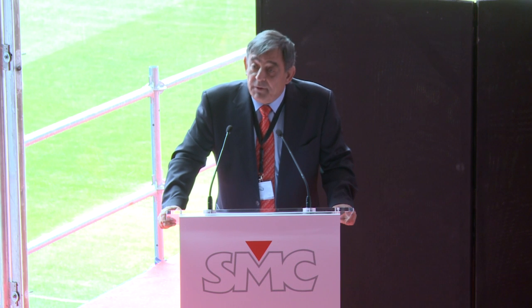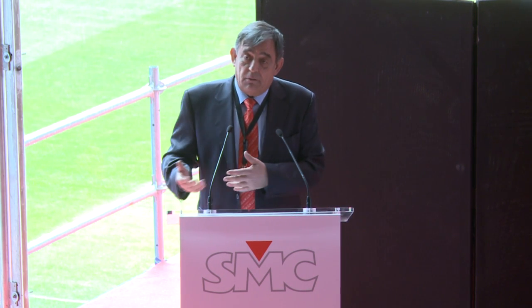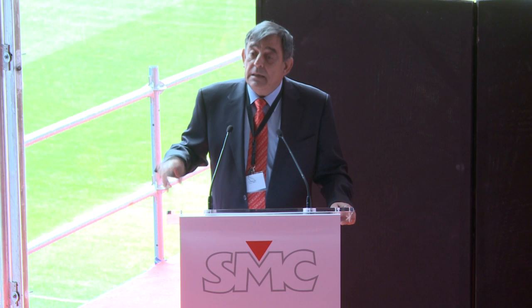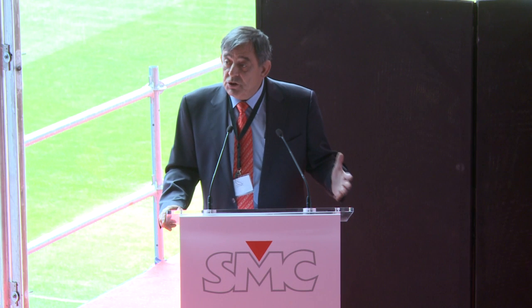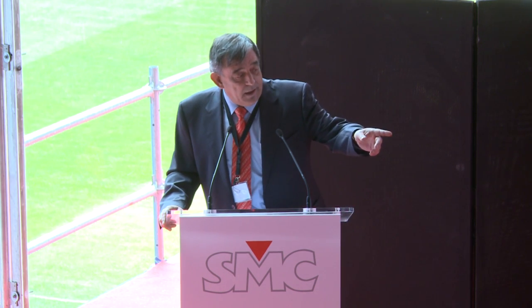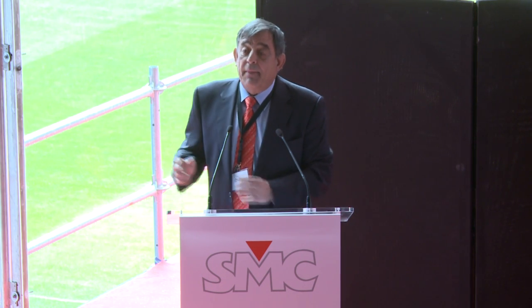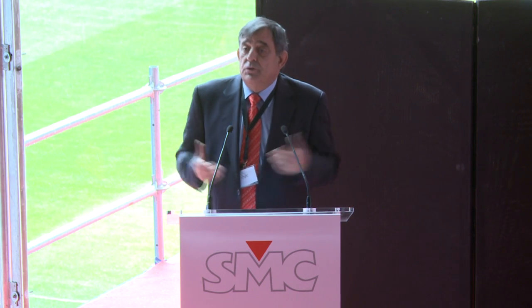Okay, this is switching technology. It's a switching amplifier, very powerful, which is in the master unit, combined with a toroidal transformer to get the current out. This switching amplifier is fed back by a Rogowski coil installed inside the equipment. So the regulation unit, in fact to generate current, is there in the master. The slaves only add power and are controlled, of course, by the control unit. So you don't need to worry, as I told you before, they are transparent for the user. They only add power, but this is the technology.